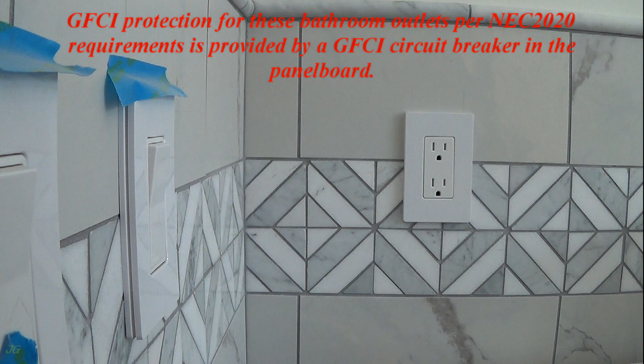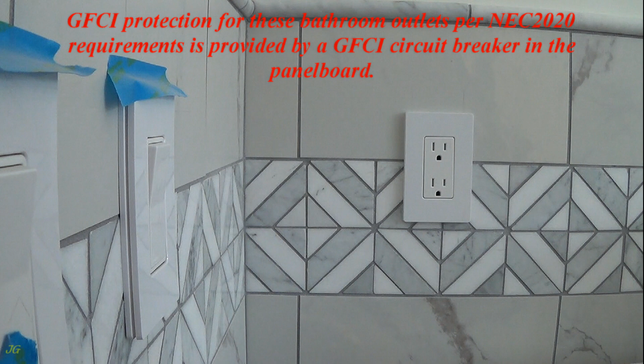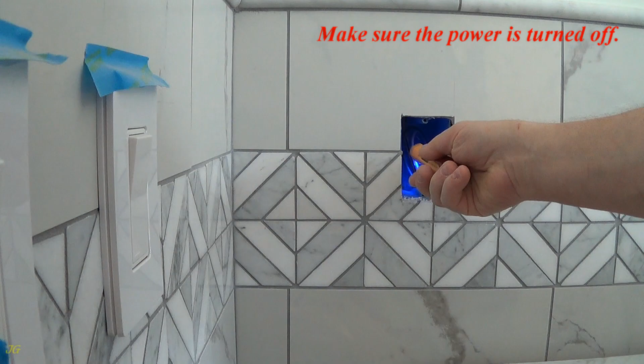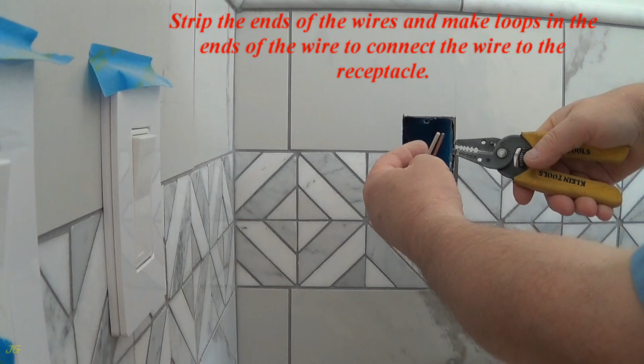Final installation of 2 receptacles for a bathroom cabinet with 2 sinks. GFCI protection for these bathroom outlets per NEC 2020 requirements is provided by a GFCI circuit breaker in the panel board. Make sure the power is turned off. Strip the ends of the wires and make loops in the ends of the wire to connect the wire to the receptacle.